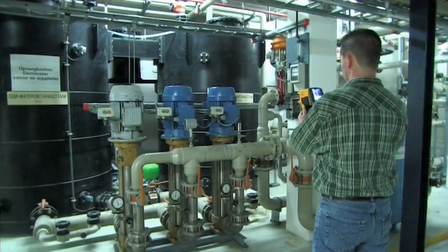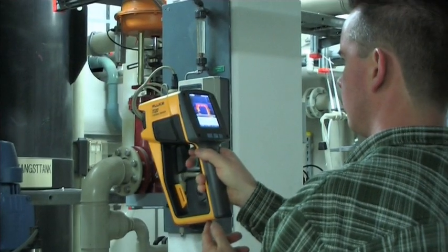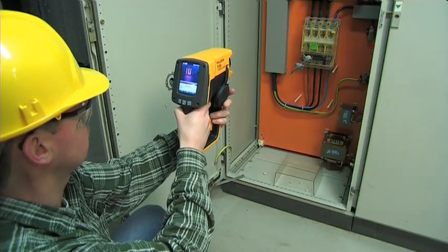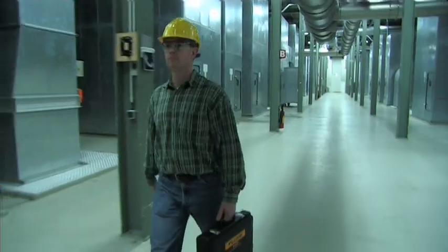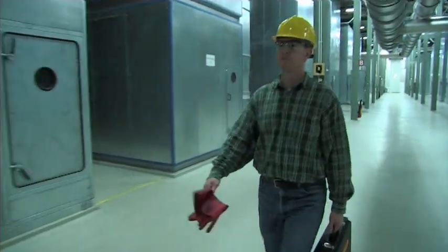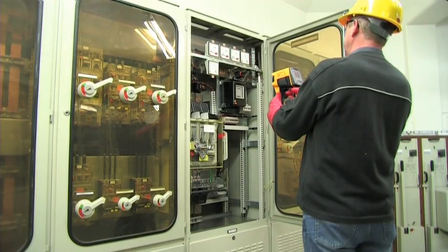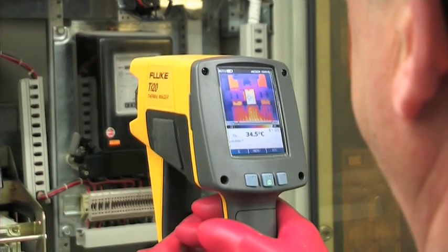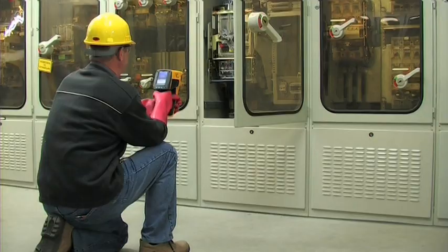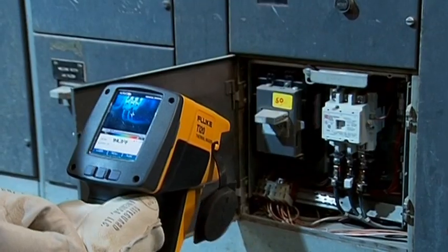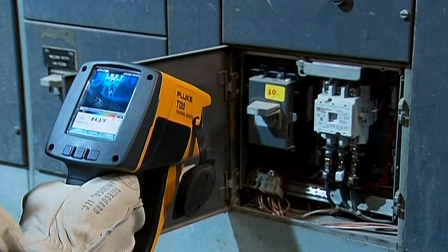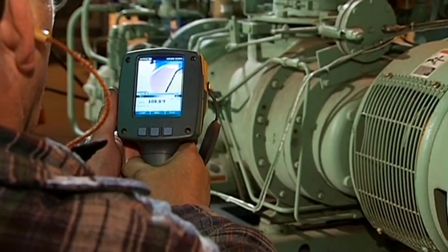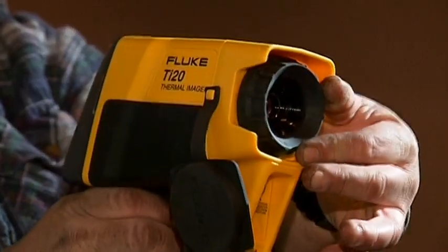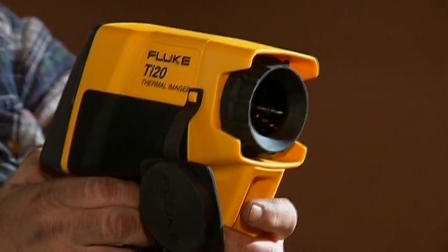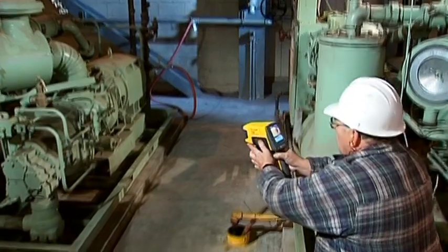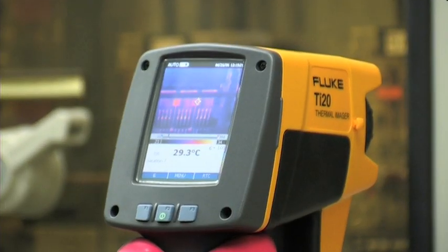Maintenance work is often carried out reactively. When a problem occurs, it is fixed as soon as possible. Thermal imaging can help you to move away from this reactive maintenance approach to a more predictive maintenance mode. By regularly taking a thermal image from the most critical equipment, you will be able to see the gradual temperature change over time. This trend information helps predict the status of your machine's deterioration. A rise in temperature signifies an impending problem. This will allow planned maintenance at a convenient time and avoids an unplanned shutdown.